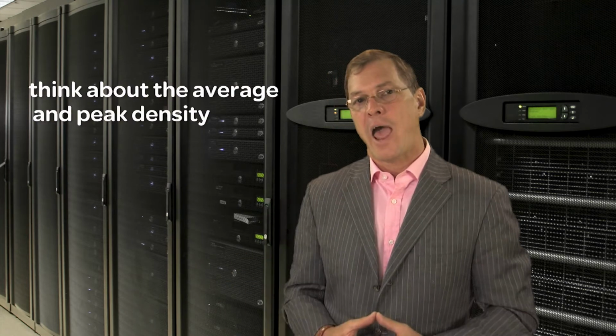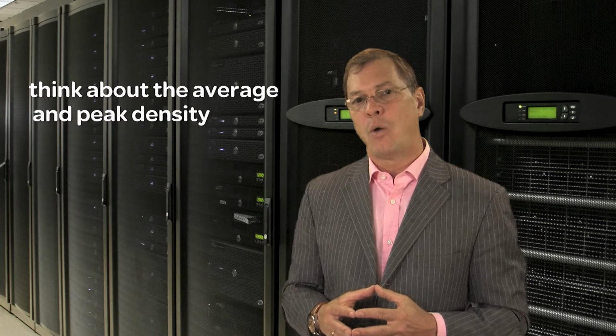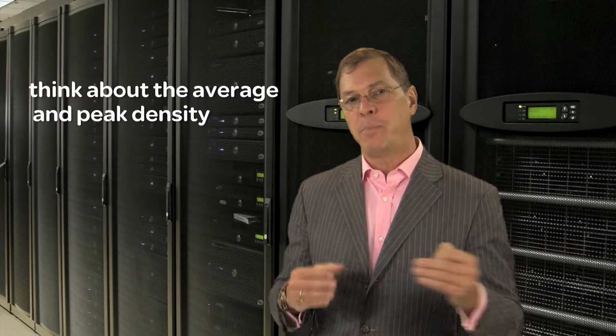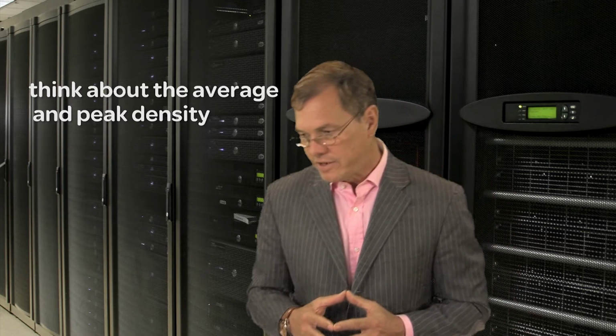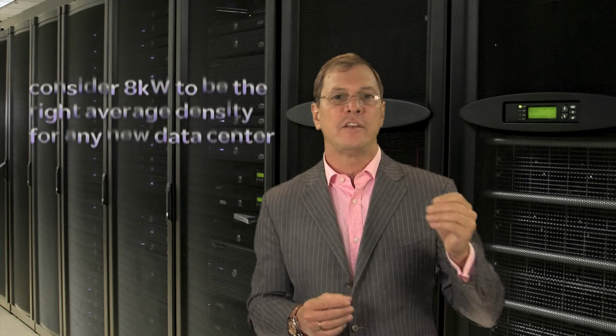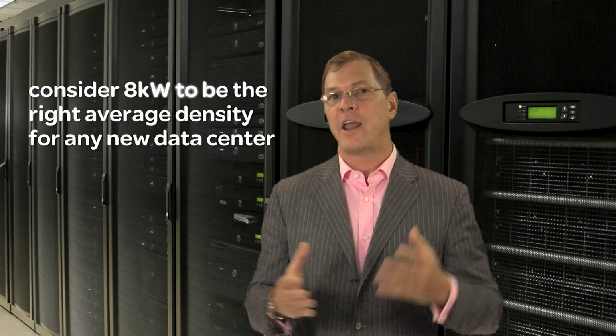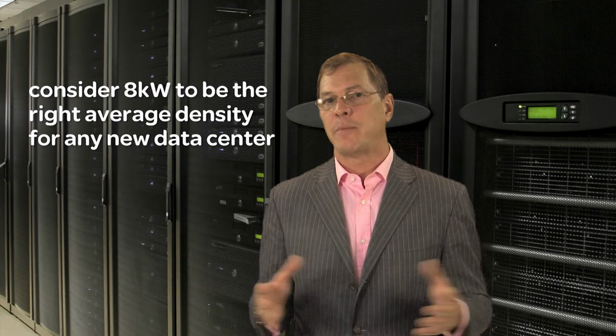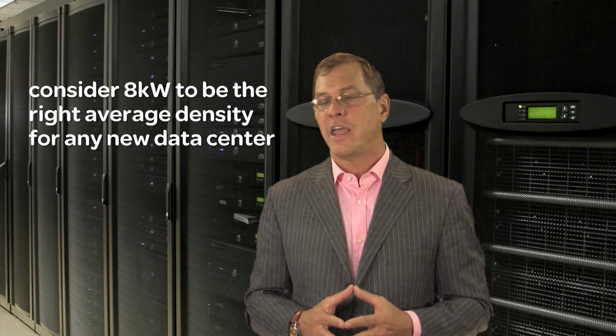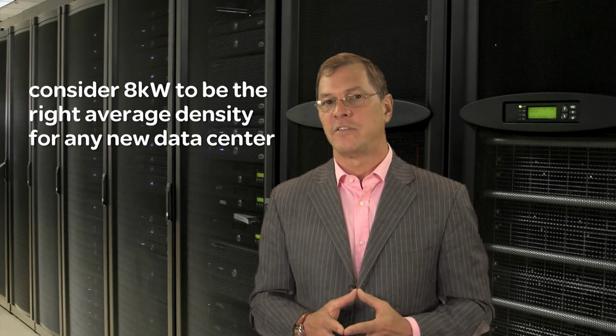The other thing that's important is to think about density. And when we think about density, we need to think about both the averages and the peak densities that we deploy in the data centers. And when we think about the average density, we need to consider at least around an 8 kilowatt average number for any new data center, even if it has a hybrid of other kinds of devices in it today, so that it has the potential to scale up into a cloud environment. And of course, that could go further.